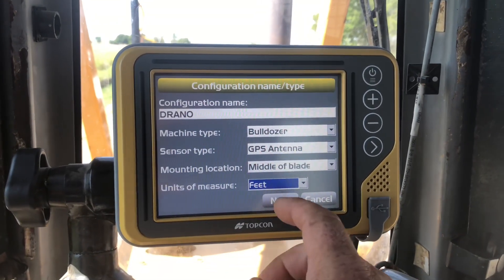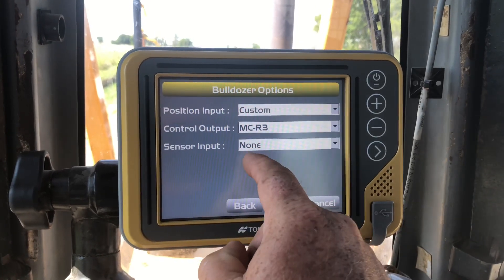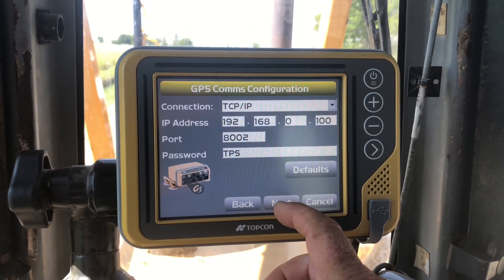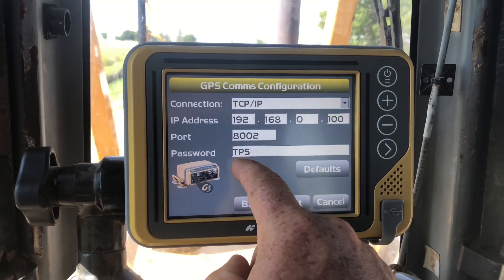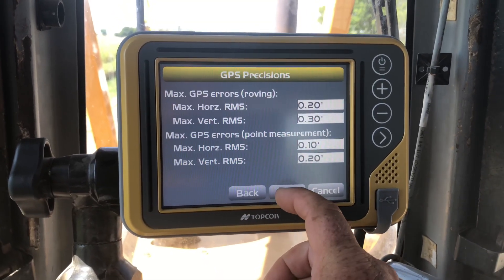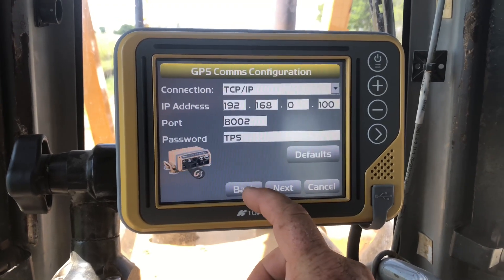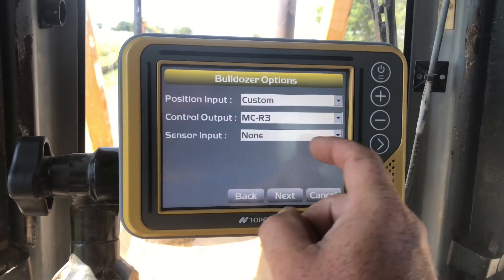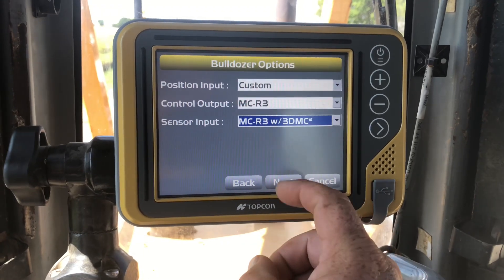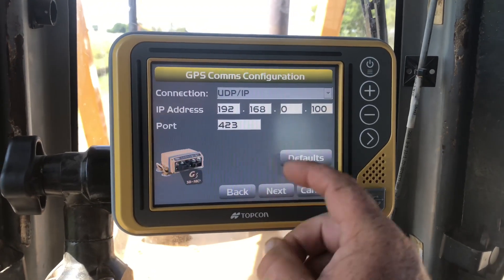So all my Drano file is is simply this: for position input, choose custom. That allows you to switch between TCP/IP and UDP. By default, if you choose or make a machine builder using MC squared as a sensor type, your port setting will default to UDP IP and you won't even get a choice to change it.